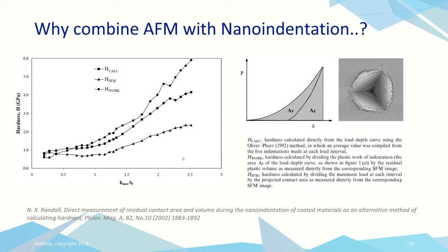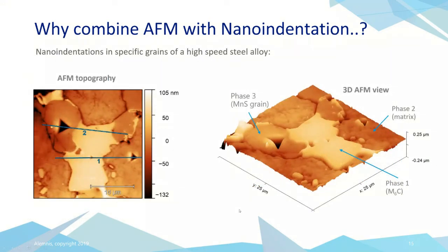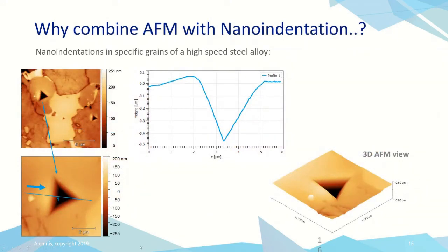And that makes sense, because when we start to take into account the pileup, then we've got a larger area for the same load, and therefore we're underestimating the hardness, if we like, or getting a lower value, which is what we see here for HSFM, which is the bottom curve. So very interesting to understand what's going on at the interface. So as Veronica showed earlier, some examples on high-speed steel, being able to zoom in on specific grains within a microstructure and then imaging those with extremely high resolution AFM. This is a very interesting technique. And we can see a couple more examples here. Taking a cross-section through an indent also tells us more about the pileup in a quantitative manner.